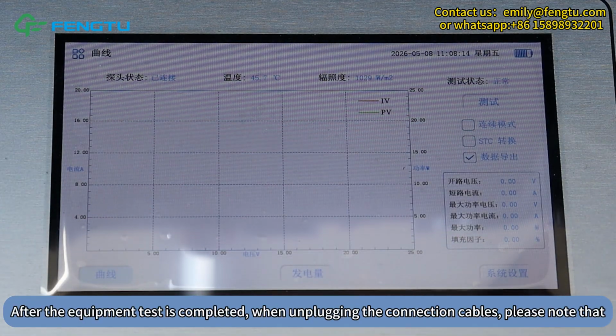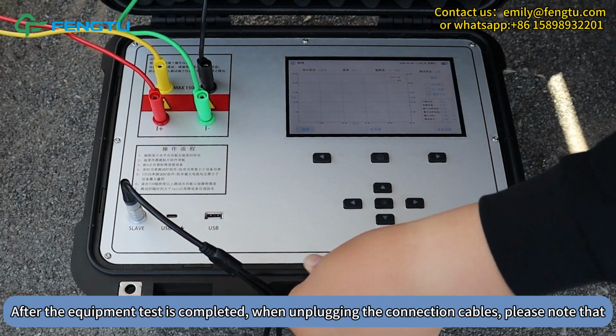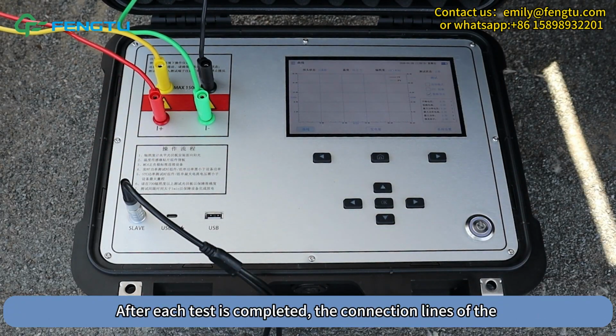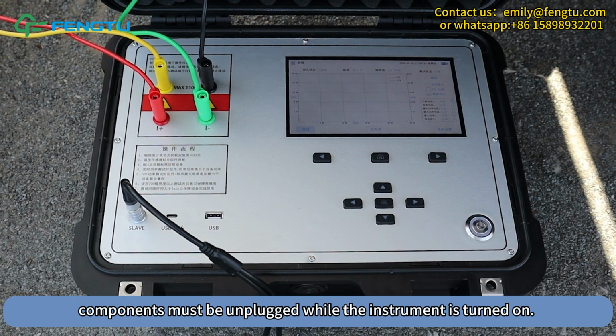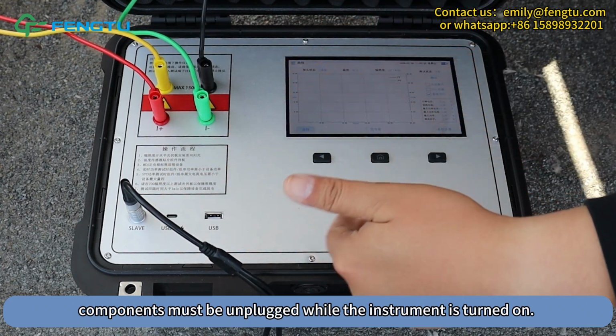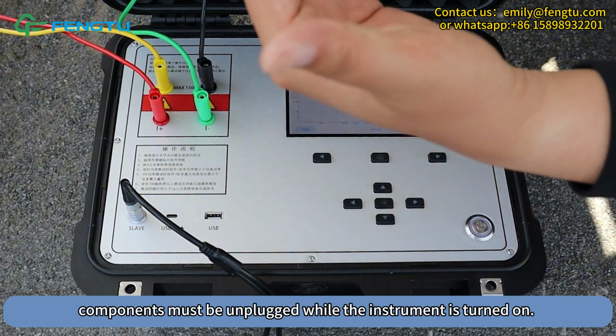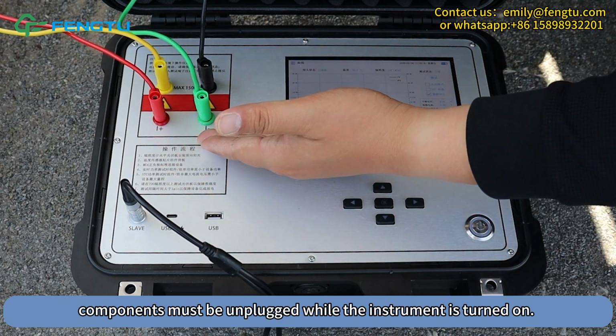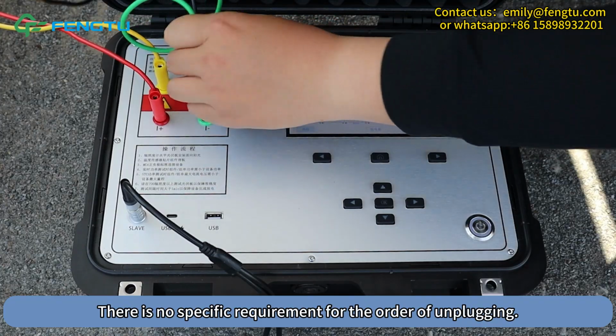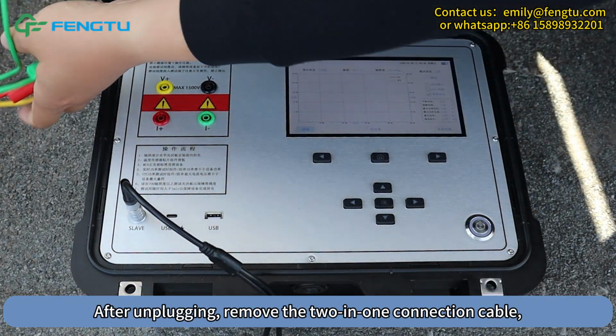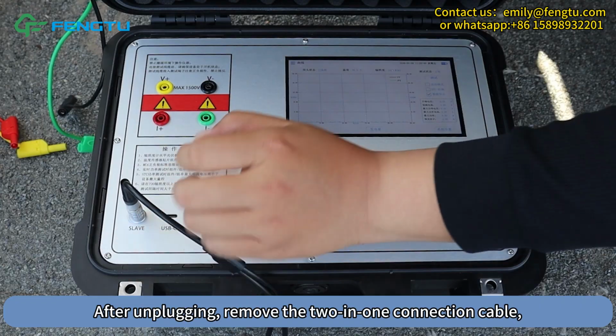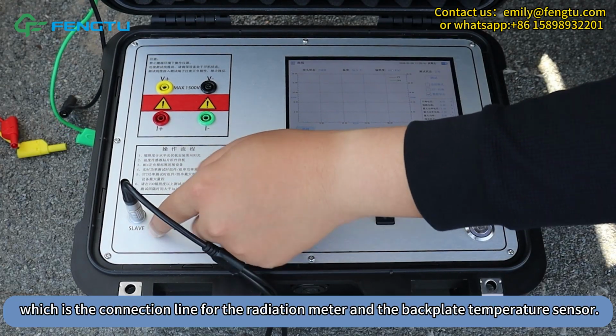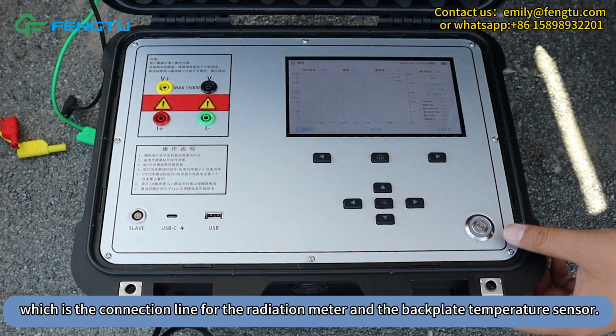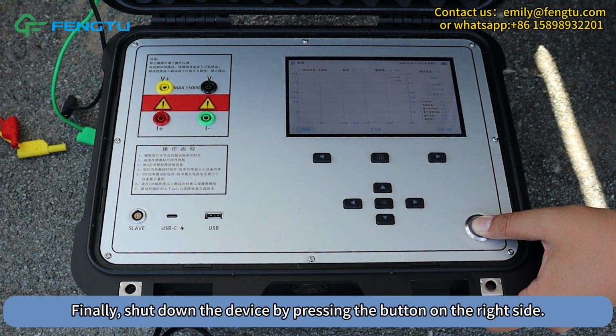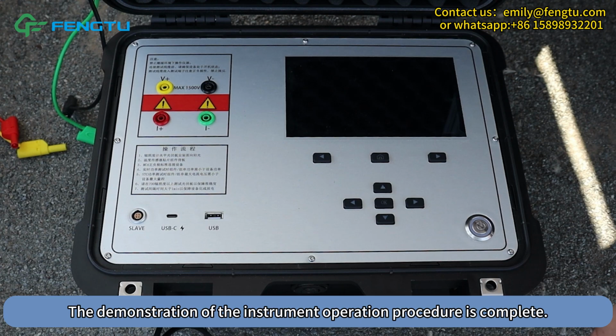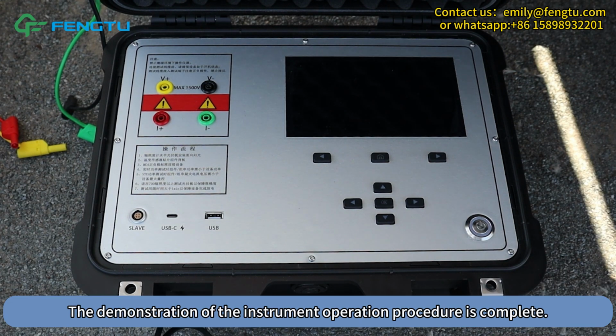After the equipment test is completed, when unplugging the connection cables, please note that after each test is completed, the connection lines of the components must be unplugged while the instrument is turned on. There is no specific requirement for the order of unplugging. After unplugging, remove the 2-in-1 connection cable, which is the connection line for the radiation meter and the backplate temperature sensor. Finally, shut down the device by pressing the button on the right side. The demonstration of the instrument operation procedure is complete.